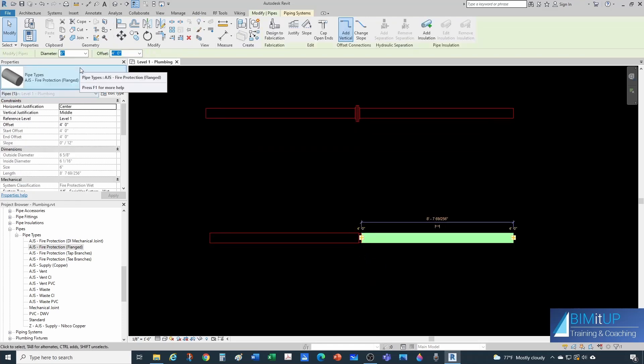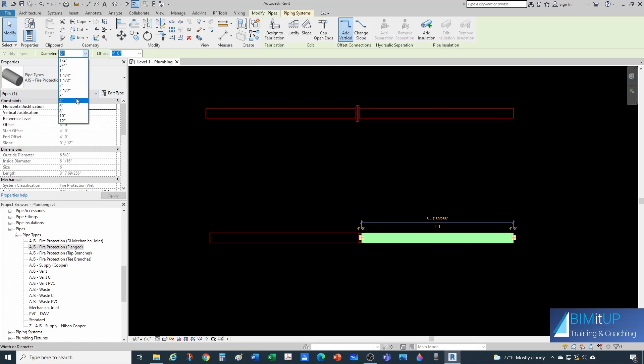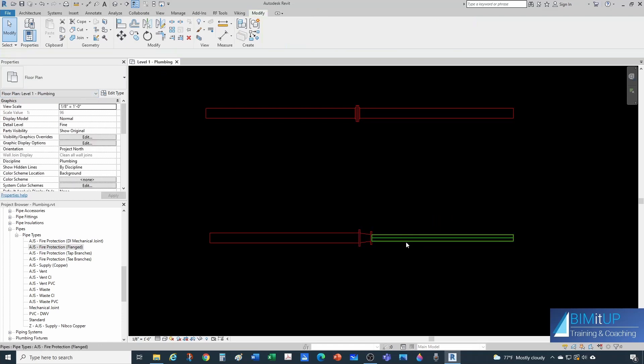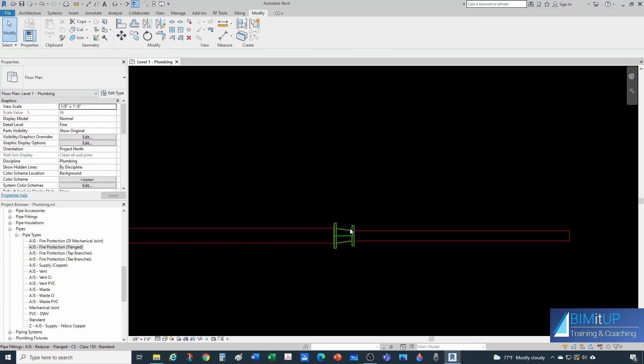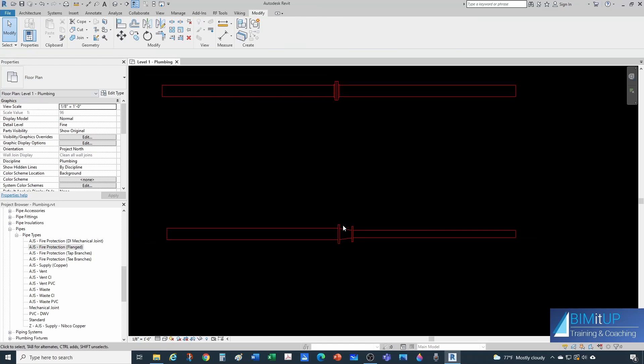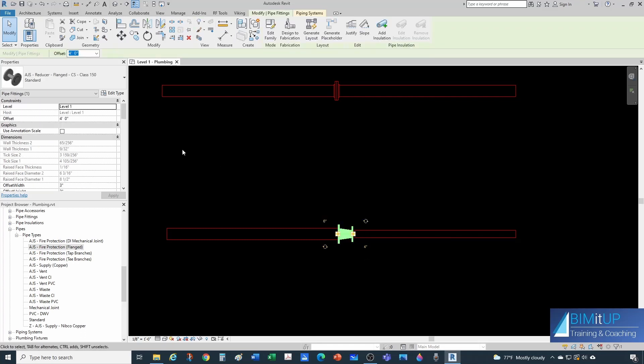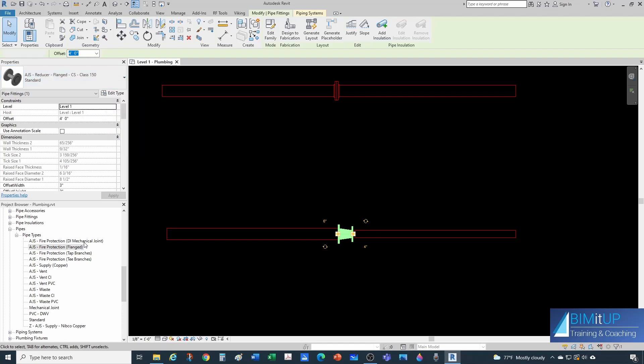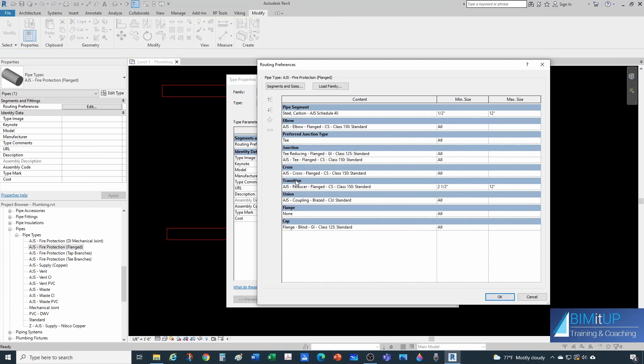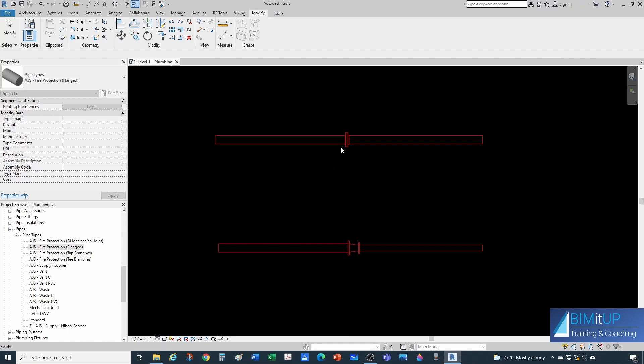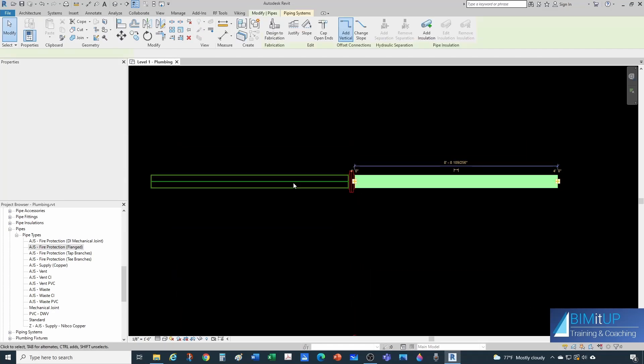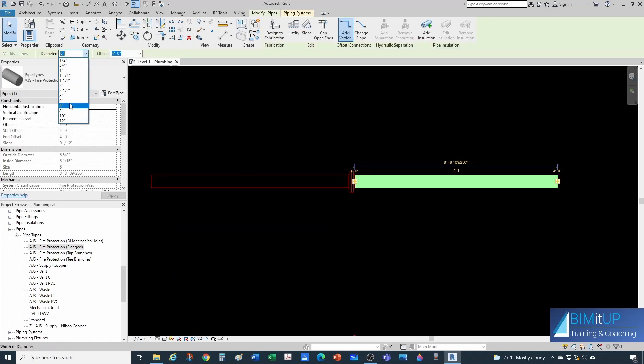Notice that when you're using your Union rather than a flange, the element created is a reducer — specifically the flange reducer that you specify in routing preferences under Transition. If you are using a flange pipe type, you can directly click on the pipe and change the size to four inches and it will identify the reducer automatically.